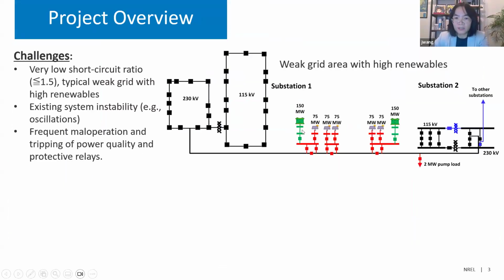So the diagram here shows you the weak grid area with the 5 solar plants, which is in the 230 kV transmission system. The line is about 100 miles away. That installed 5 solar plants, as you can see here. Each of them is 75 megawatt. And FPL plans to install 2 bigger grid forming inverters, each 150 megawatt.